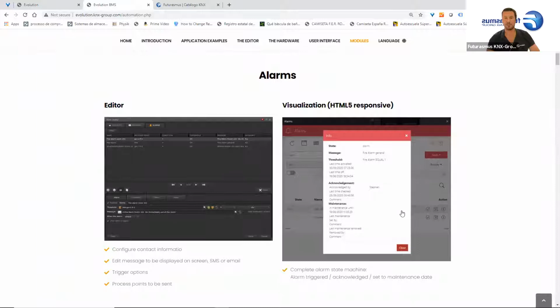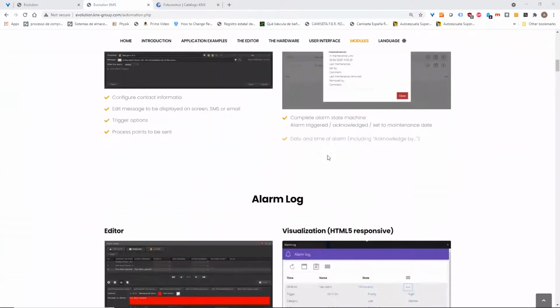If it's acknowledged but not gone away yet, you can set it in maintenance mode, and then another pop-up can come up after a time, showing you if the maintenance was not done in that time. You can see the full history log of everyone who acknowledged the alarms, with the date and time they did so. So it's a very complete feature.